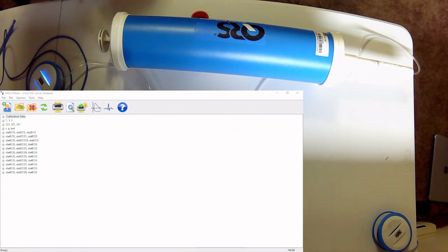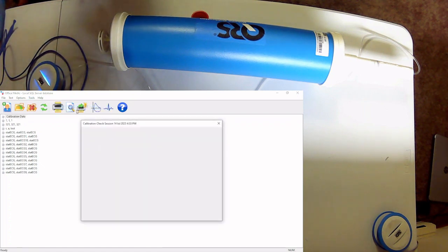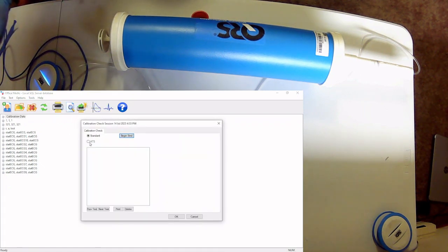All right, next we'll need to get into our Office Medic program. And we are going to go into Tools, Spirometry, perform a calibration check. There's two options here. There's standard and ATS. Standard is for my more scientific legacy type things. We're going to go to the ATS standard, or ATS calibration check, which is a 1 second, a 3 second, and 6 second. We're going to push 3 liters of air in 1 second, 3 seconds, and 6 seconds. So let's go ahead and get that started.